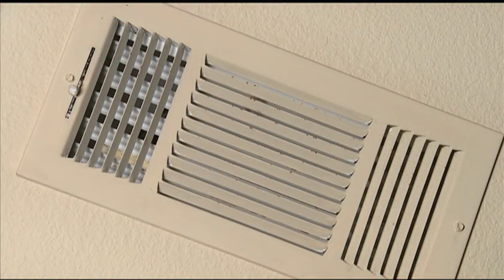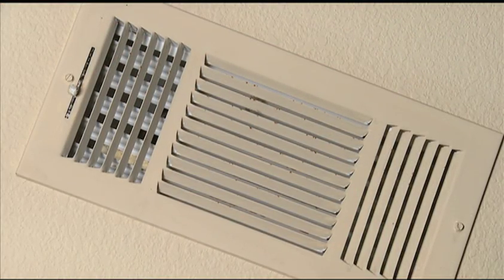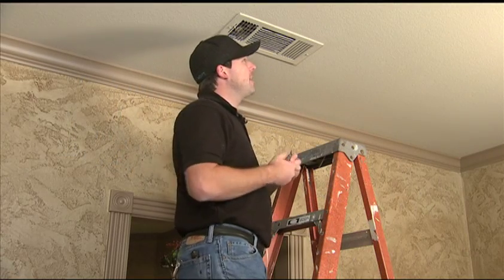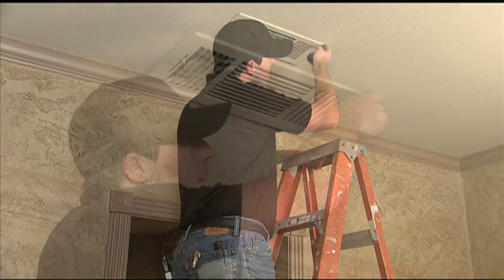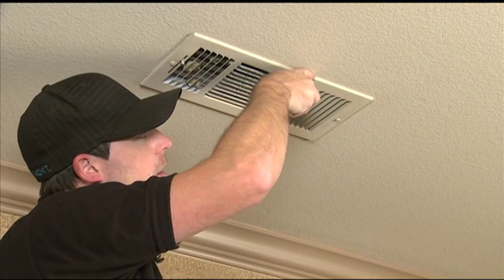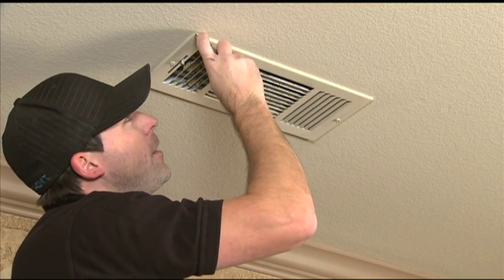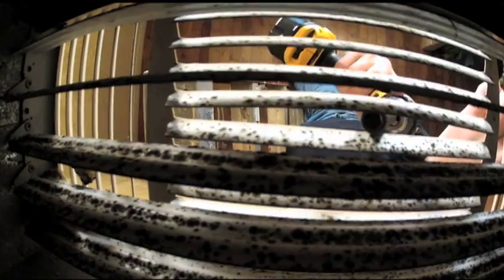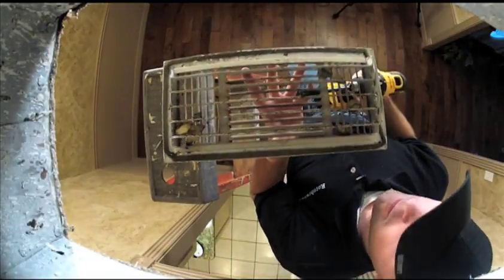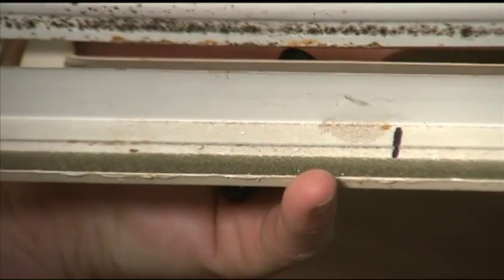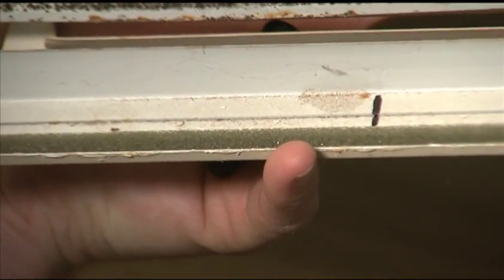You may find a register that's painted, which this one is, or it may be caulked, or it may freely come off. If it's painted on or caulked, you're going to use your knife and cut from the corners in. If you go all the way off the edge, you've got a good chance of marking the entire wall. Once you get it off, you'll topically clean the register and the boot opening if there are heavy contaminants. You'll want to mark it. That way when you go to clean it outside, you'll know exactly where it goes back.